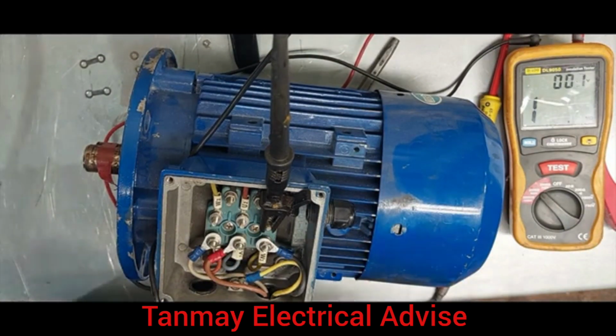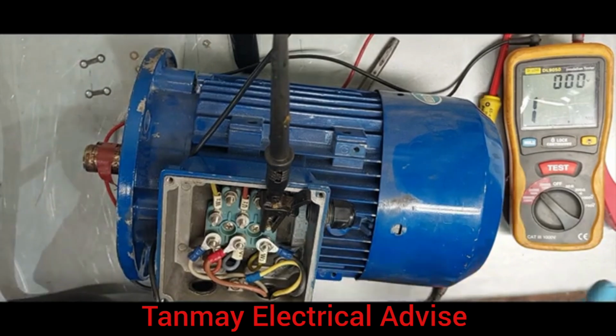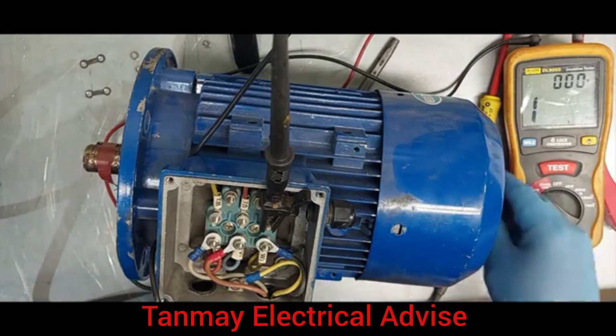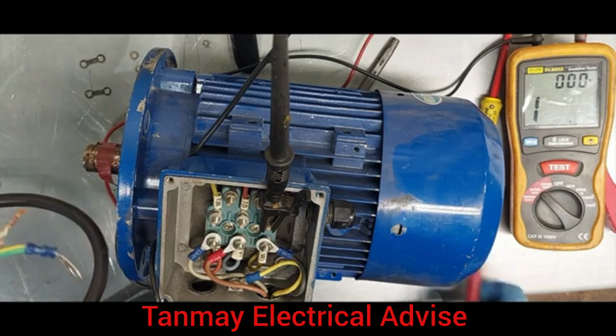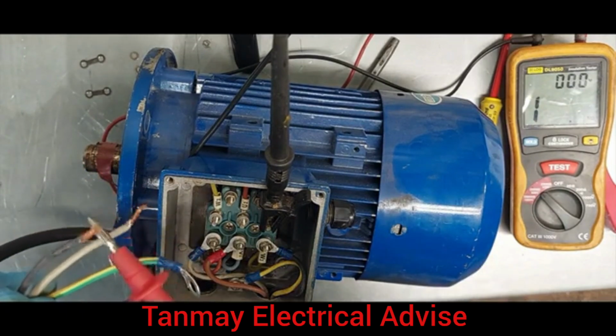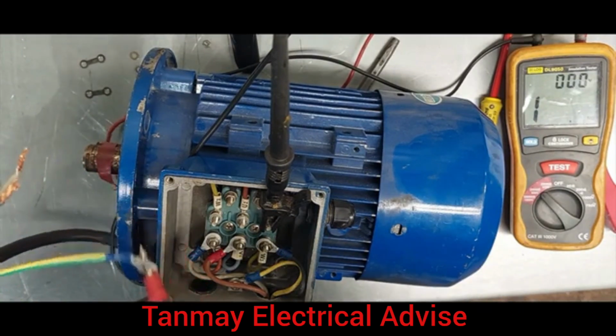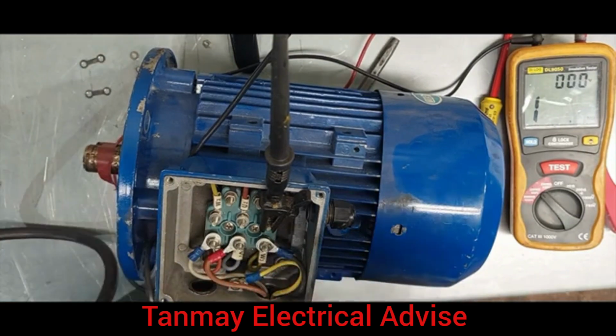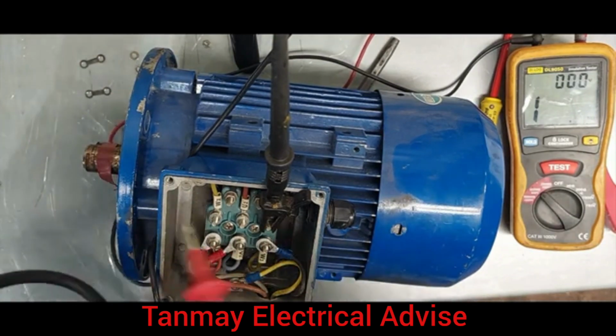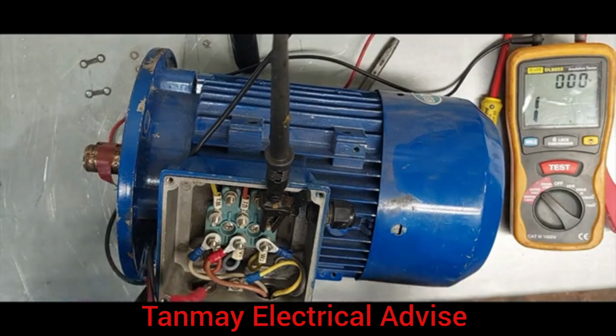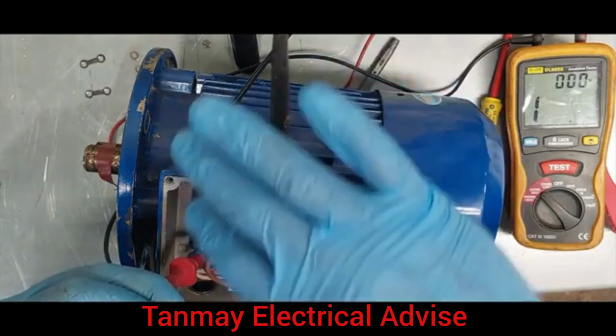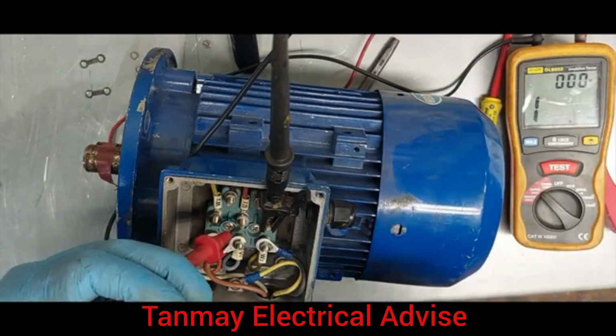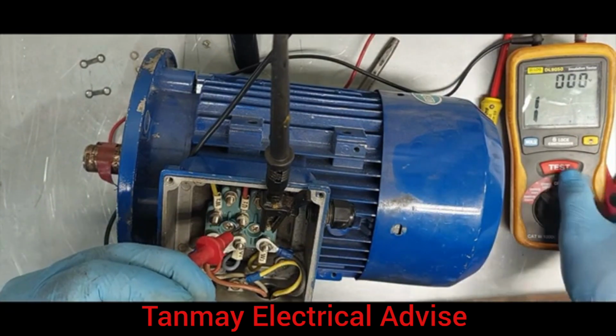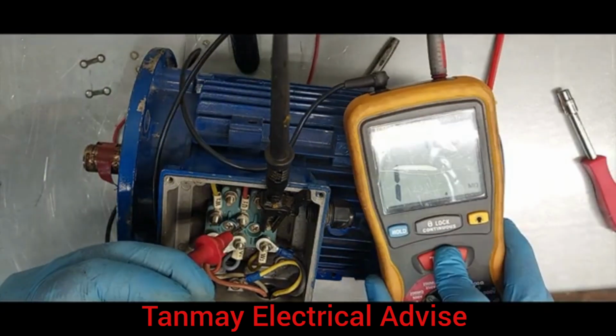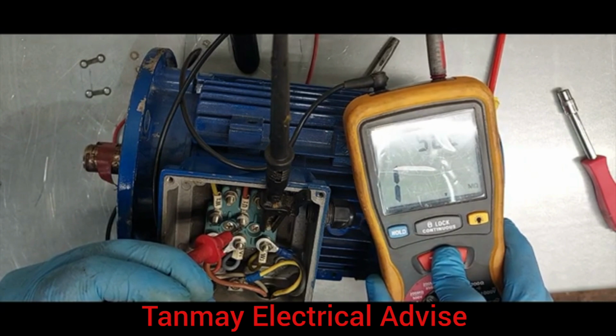So once we've tested all this, and if it passed everything, now we can test the cables. We can do the same test between each of the cables and each other. We do tests between the cables, the wires, the conductors. So we can do a test between V2 and U2, for example. We inject 500 volts between U2 and V2. You see the insulation between them is good.